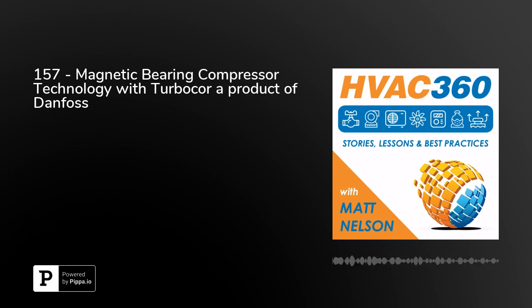Oil, when applied in a chiller system, doesn't really do you any good—in fact, it inhibits efficiency and performance. So when you remove oil from the equation, you get better efficiency and better long-term performance over the life of the compressor. The other benefit is that removing the oil management system significantly reduces maintenance tasks. All the traditional maintenance associated with oil—changing the oil, changing the oil filter, taking weekly oil analysis—that's gone. You no longer have to do that, resulting in significantly reduced maintenance tasks.